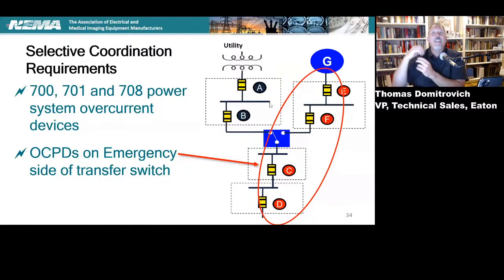So you're guaranteed that any fault that system sees, whether it's an overload, a ground fault, an arcing fault, or a three-phase bolted fault, you know that device D is going to trip before device C. In a coordinated system in the 0.1 second world, the only thing you know is that in an overload, device D will open before device C, but you don't know anything else. So that's been the battle between the two.